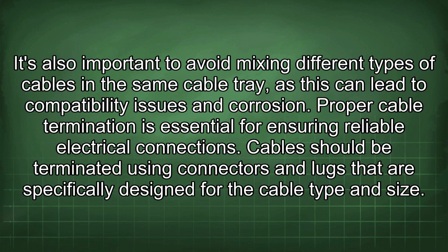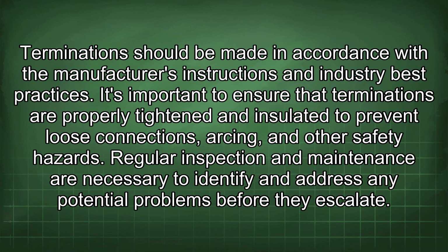Cables should be terminated using connectors and lugs that are specifically designed for the cable type and size. Termination should be made in accordance with the manufacturer's instructions and industry best practices. It's important to ensure that terminations are properly tightened and insulated to prevent loose connections, arcing, and other safety hazards.